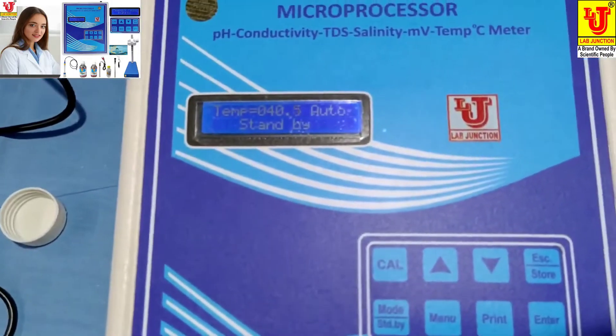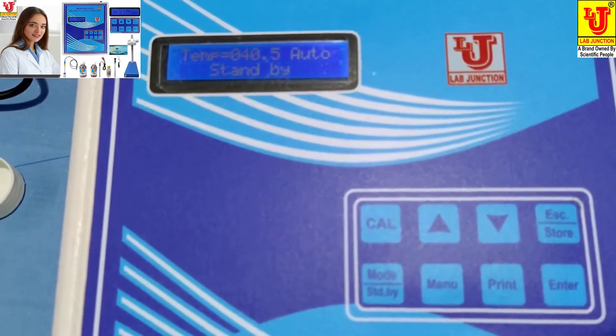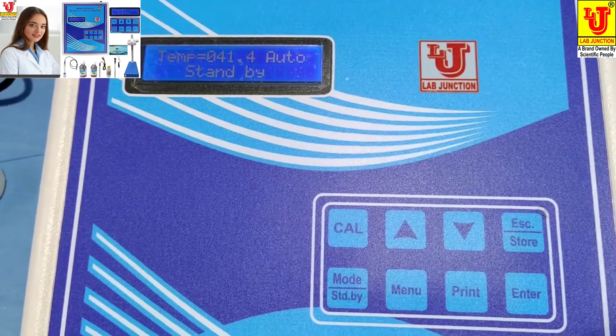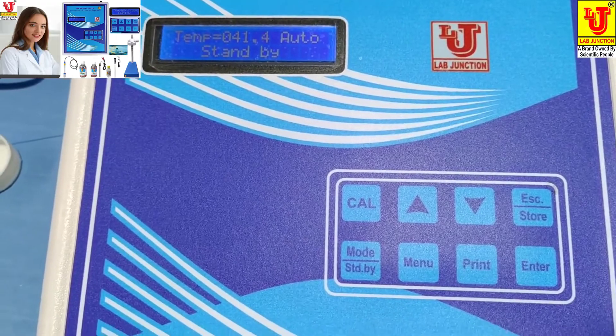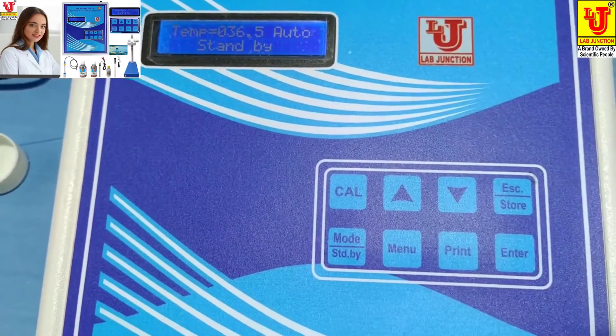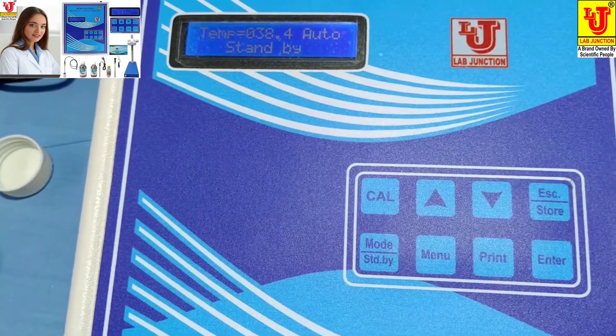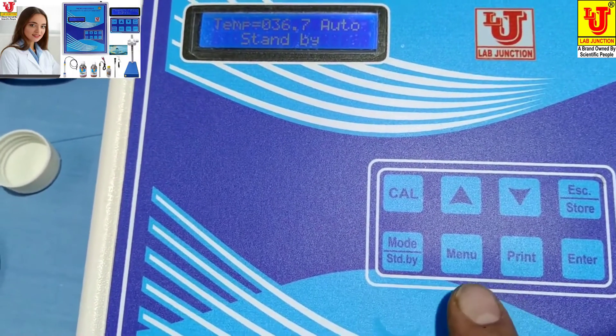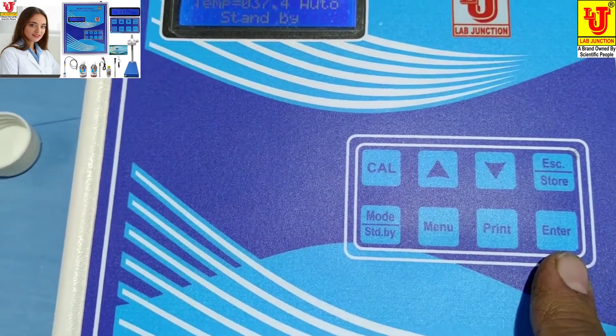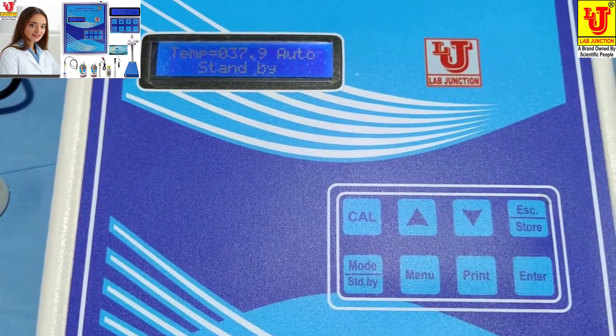At the top it shows temperature and standby. Now, how to calibrate this. There is the CAL key, up and down keys, escape and store key combined in one key, mode and standby key, menu for selecting parameters, print for printing results, and enter for confirming.